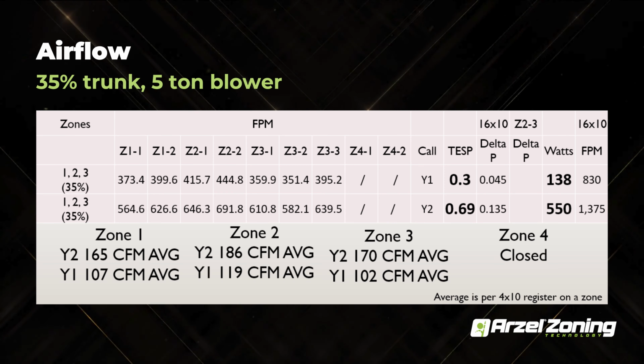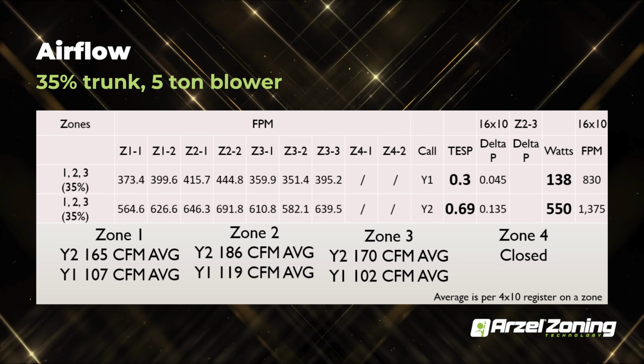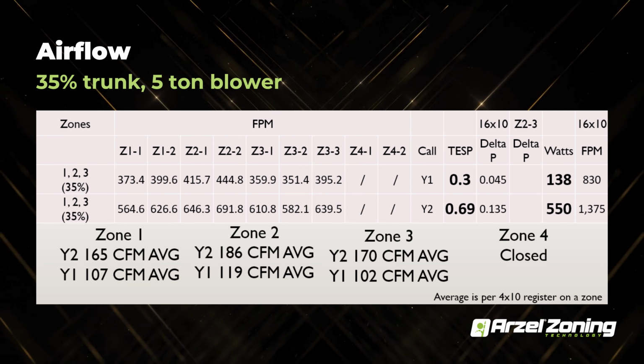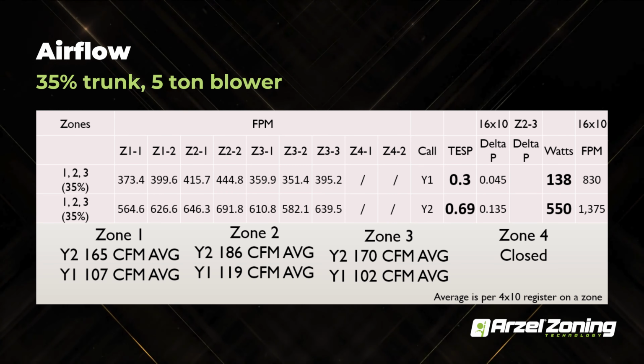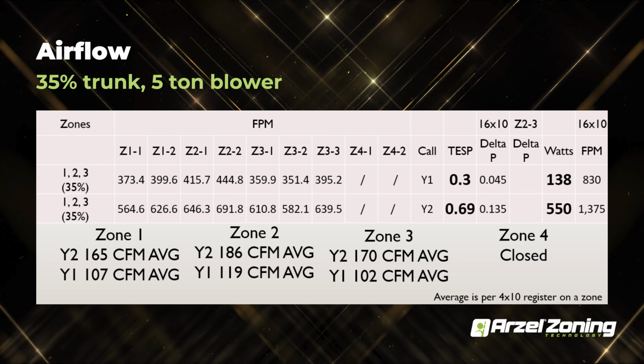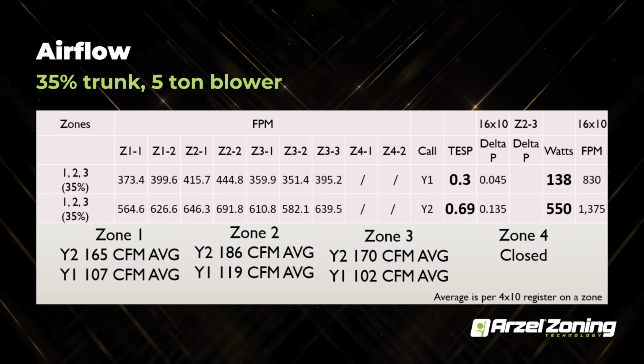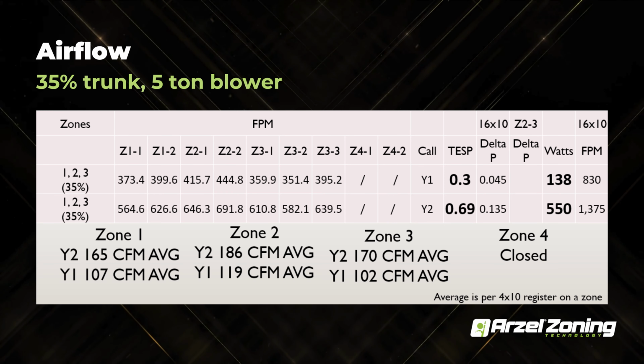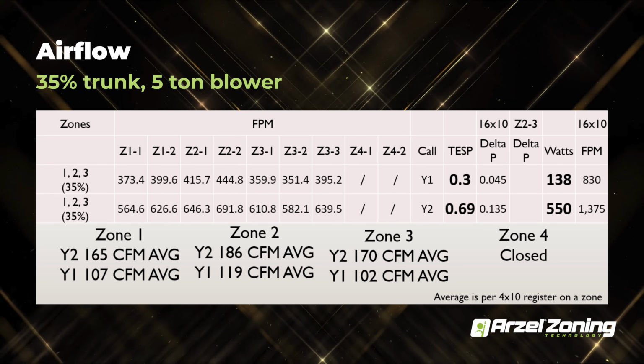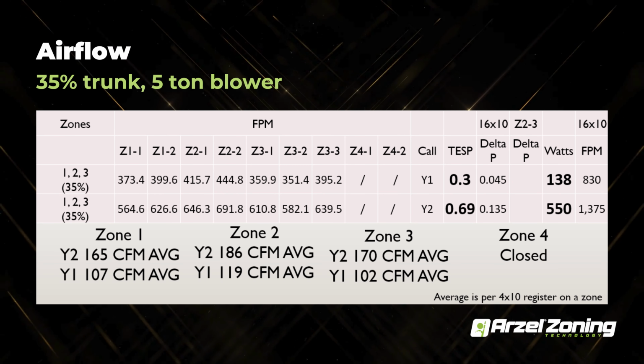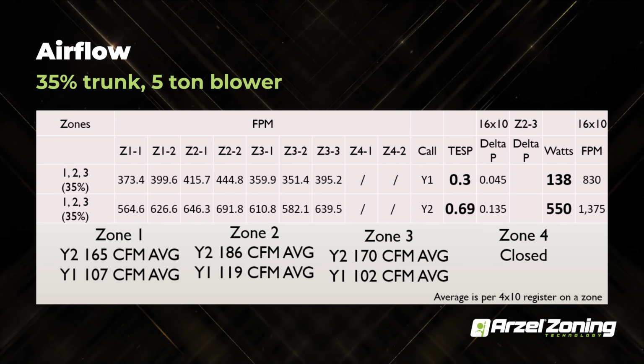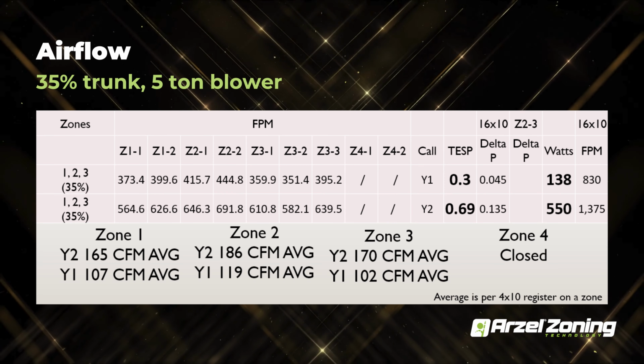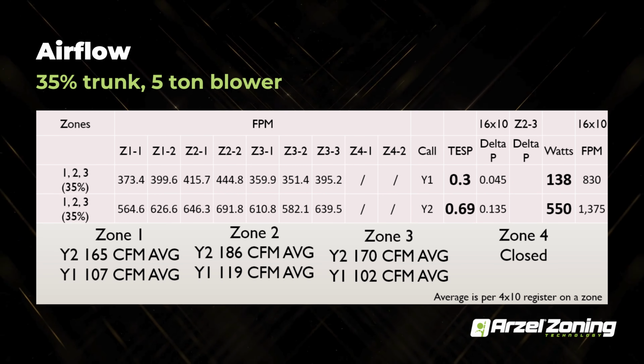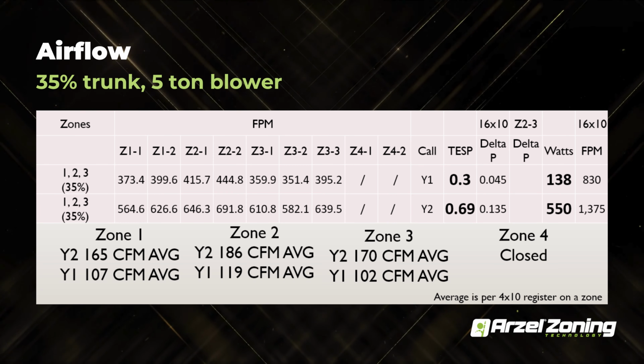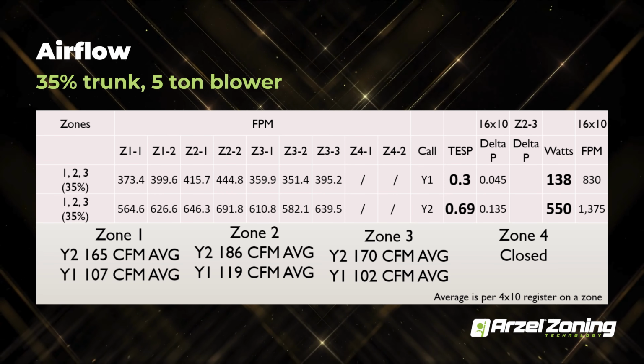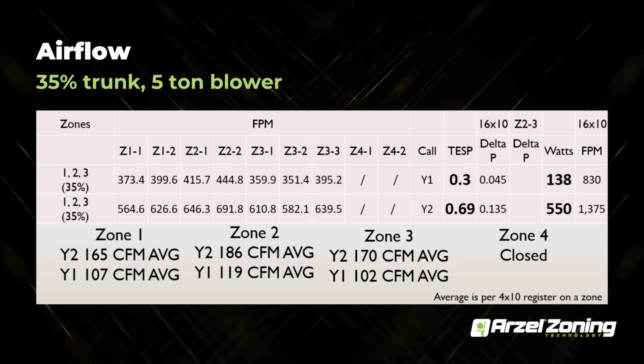But with this setup here, with our Y1, we were able to maintain that 0.3 static and a 0.69 on Y2, and the difference in wattage is 138 to 550. So this is essentially dropping it down, locking in the first stage. You can see the difference in wattage, but our feet per minute is not that far off. We have 830 feet per minute on first stage with the same thing, and then we have 1,375 with the other zones open and a Y2 output.